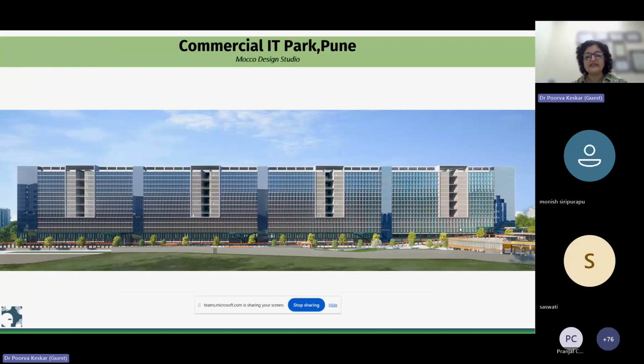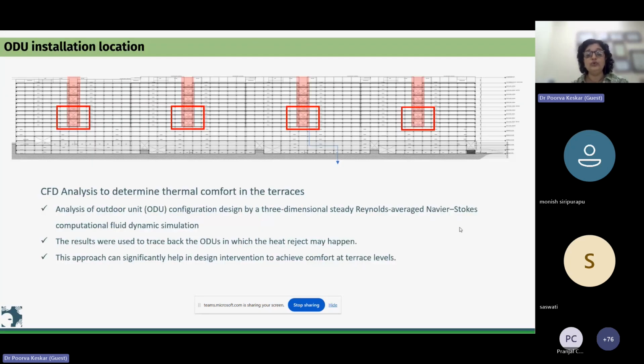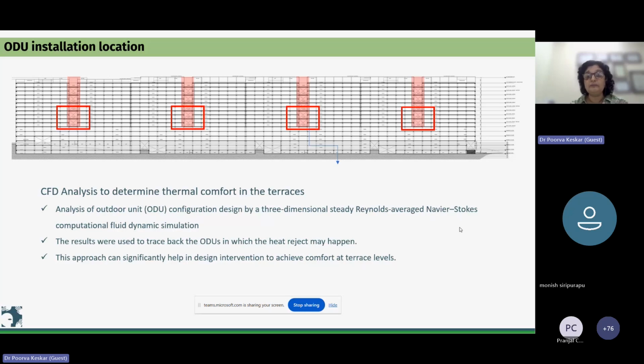So we started with this facade, and the terraces the architect had created were going to act like breakout spaces for occupants, since this was an IT building and people wanted to come out to the terrace and enjoy some open air before going back in. But the problem was that these terraces were also going to be used for the outdoor units of the air conditioning. The issue is, once the ODUs go there, what temperature results in the terraces, because the ODUs leave heat there and could reduce usage of the terraces, since if the temperature gets too high, people won't be comfortable coming out.